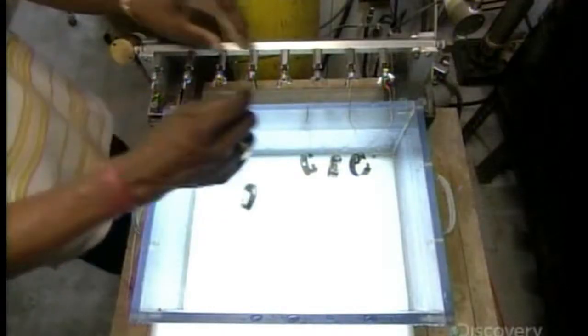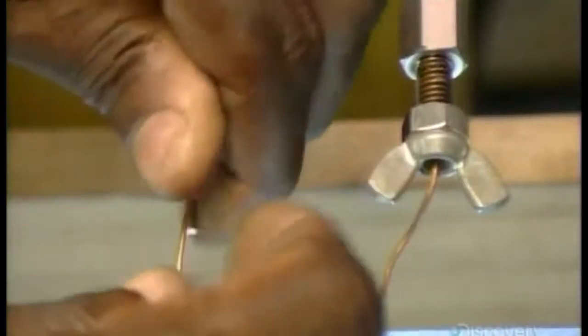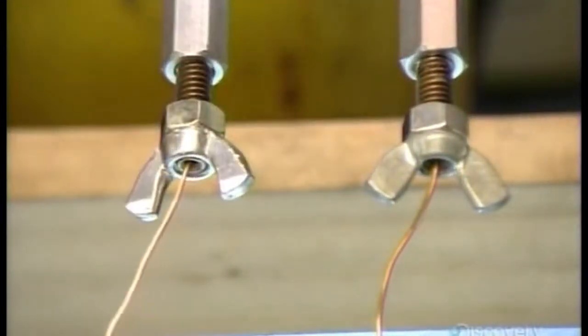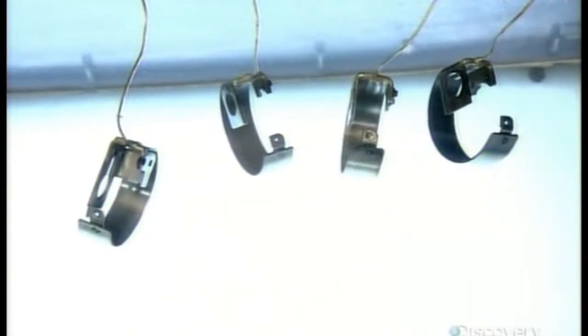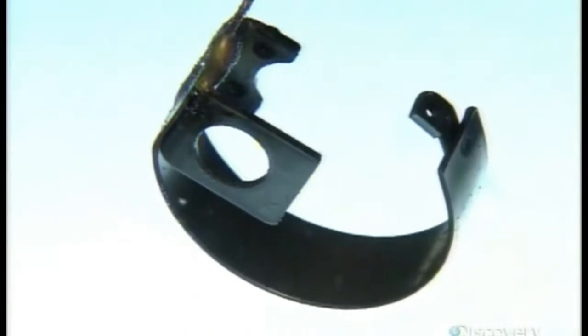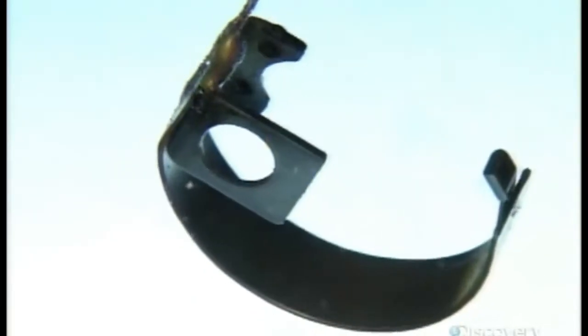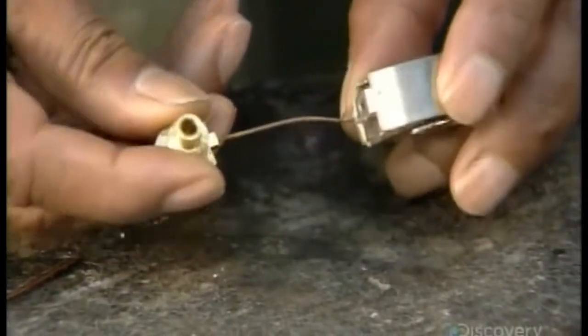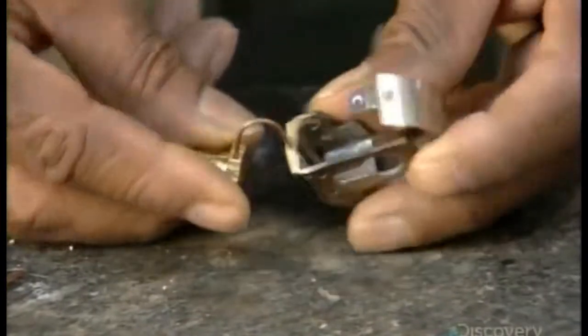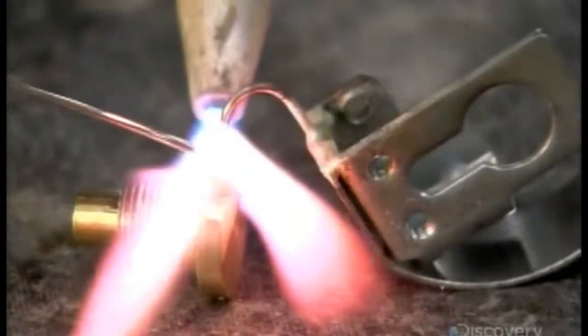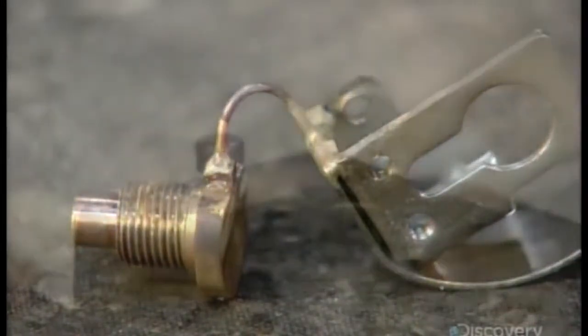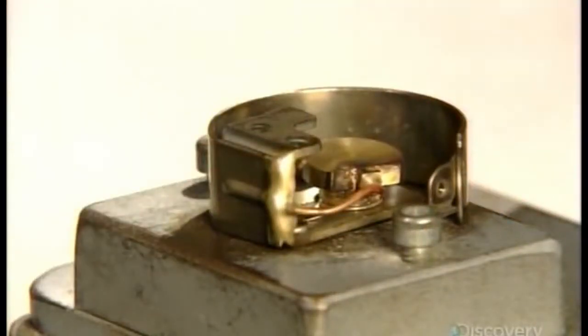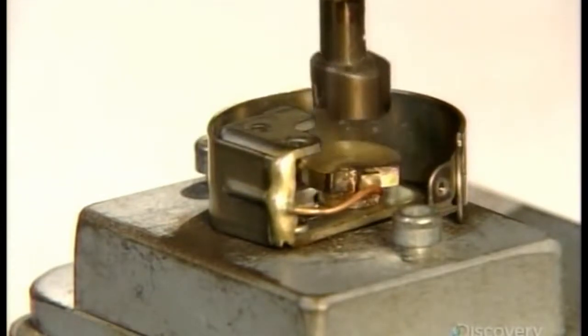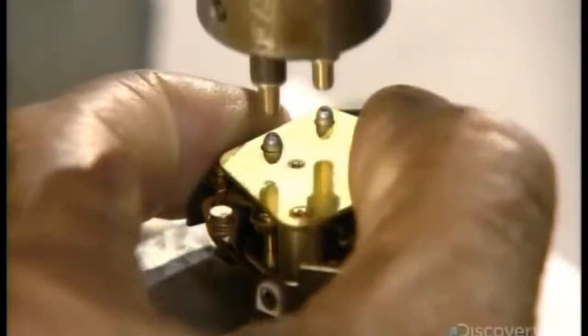Now a test. He pumps gas into several Bourdon tubes and immerses them in water. If no gas bubbles out of the tubes, it means the tubes are perfectly sealed. The gas pressure also causes the tubes to spring into action. It's this action that will move the pointer on the dial of the thermometer. The next worker attaches a brass connector to the tubing. He brazes them together to create a solid bond. He folds the brazed parts into the curve of the Bourdon tube and pushes it into place with a mechanical press.